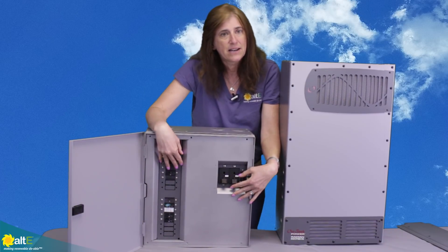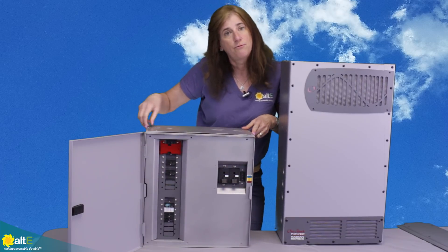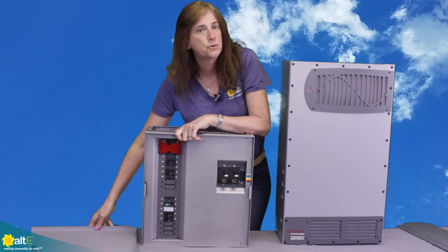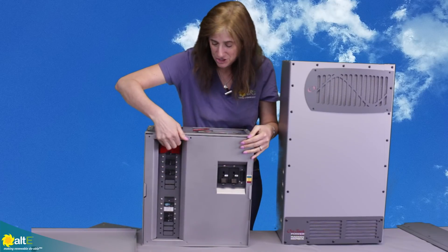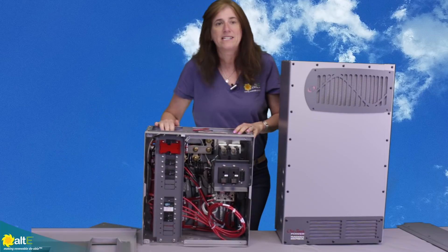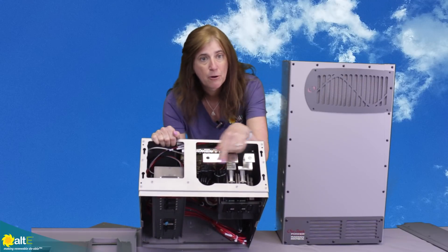It's got all these different slots here. What's really nice is you can just take out four screws off the top and you can remove the cover. So if we also take off the door and take off this front panel, I can really show you a lot of the different capabilities of this breaker box. When I take the top off, that exposes these power bus bars.